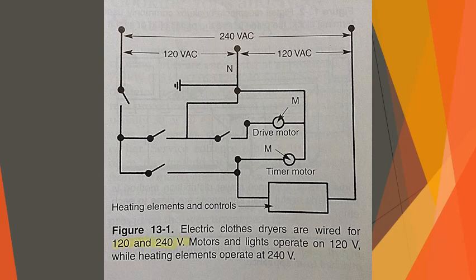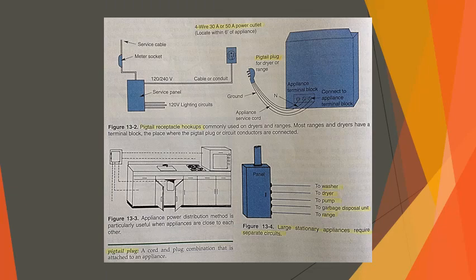With only rare exceptions, the appliance is connected directly to the power panel. It is protected by the branch circuit breaker that also may serve as a disconnecting means. Most hookups are made with a pigtail plug, a short cord and plug combination that is attached to an appliance, and a receptacle. This is a common practice with clothes dryers and electric ranges, see figure 13-2. The pigtail receptacle method involves running the conductors from the service panel to the receptacle. Then, through the use of the pigtail plug, the circuit is completed to the appliance.